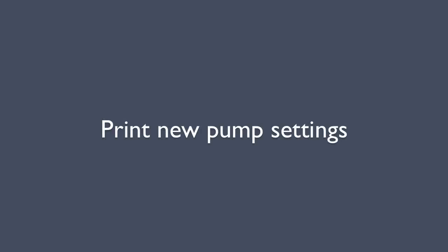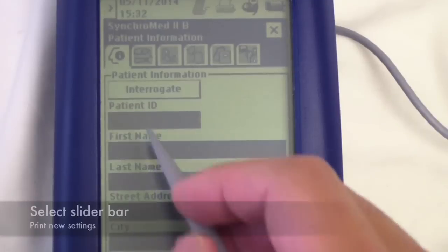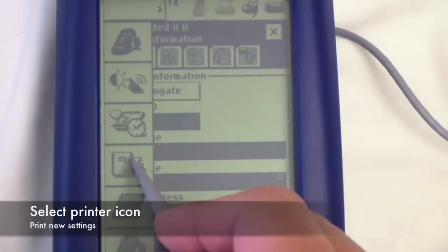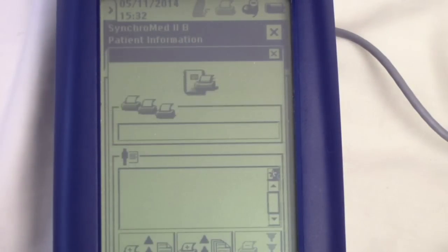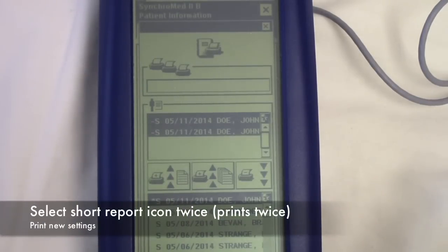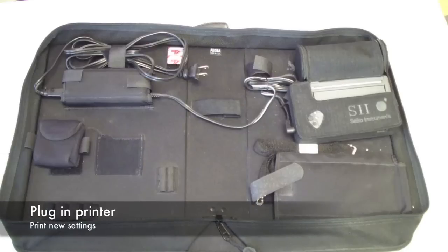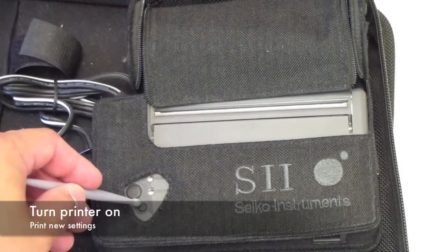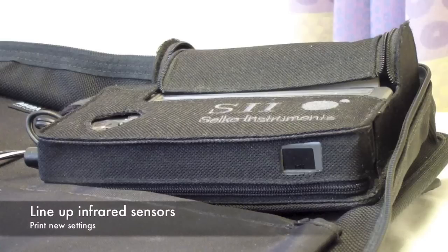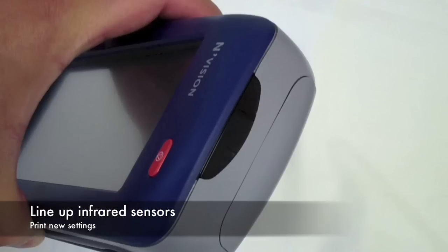Print the new pump settings out any time changes are made. Open the slider bar in the top left corner and select the printer icon. Add the short report to the printer queue twice. Line up the infrared sensors on the printer and the interrogator, and it will start printing.